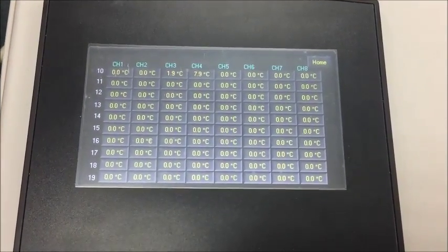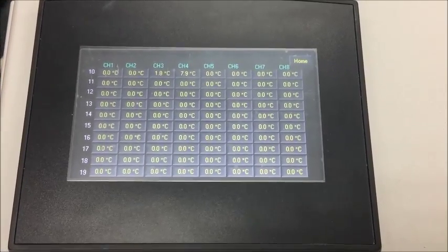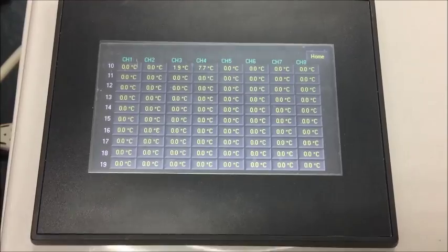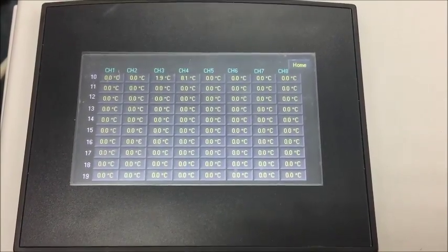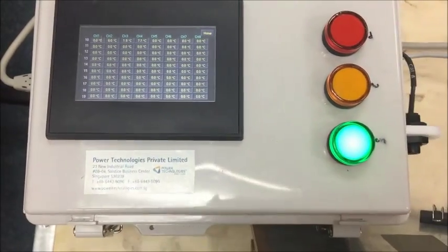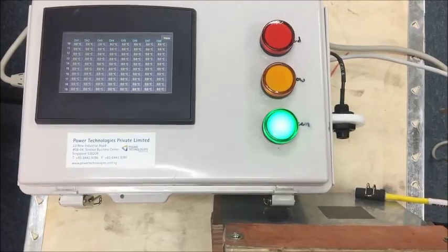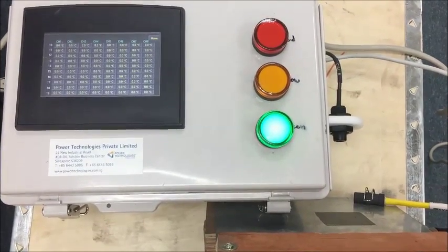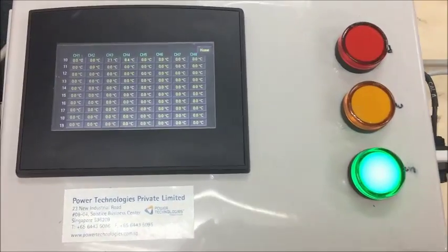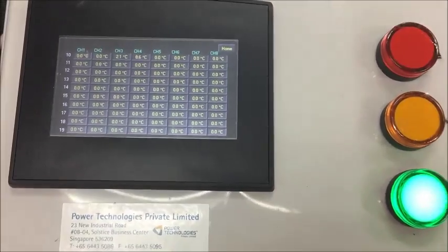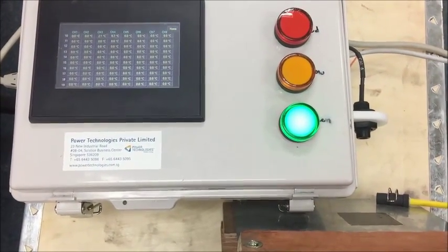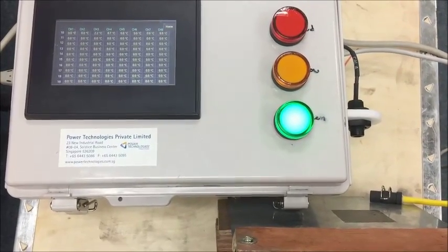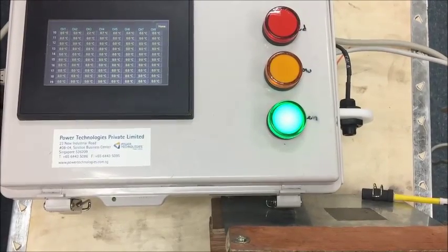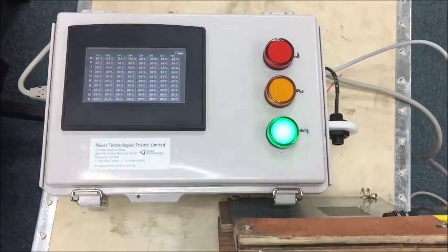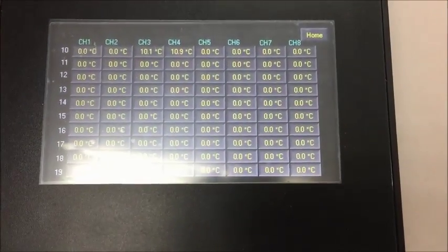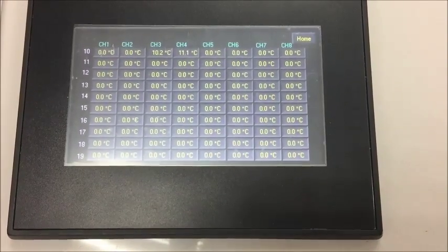So you can see here the temperature gradually increases. Once we detect an abnormality, arc flash will not happen immediately. It takes a while, according to the NETA standard itself. And our system will not create a false alarm. There may be times when there's a transient or a spike of voltage that heats up the surface, so it will not immediately send any response, to prevent false alarms. So you will see it gradually increase, from channels 3 and 4.